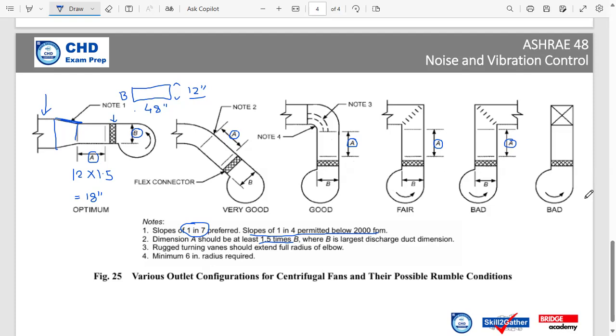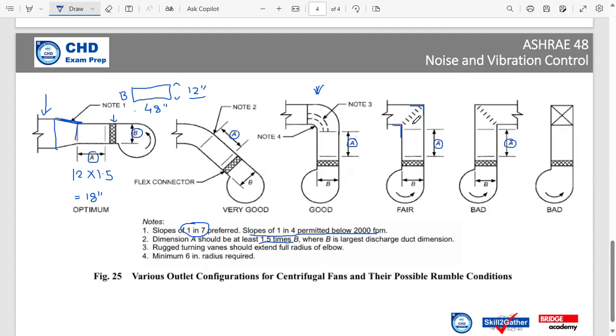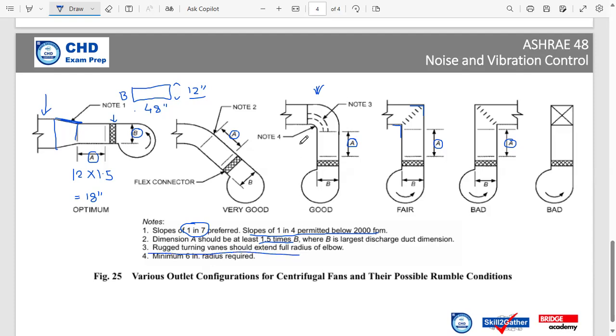Now looking at these 4 pictures, it is very easy to understand. This is the optimum scenario if you want to throw air upward vertically. If you see the second picture here, the angle is very sharp, so you are not going to get good performance here. A high amount of loss will be similar to this and this, so these are not acceptable good performing conditions for centrifugal fan. But if you are throwing air in vertical upward motion, this one is the ideal implementation to follow. Everything is the same, only different is the turning vane. You need to provide vane here in case you are throwing at upward motion, just to get the laminar flow faster.